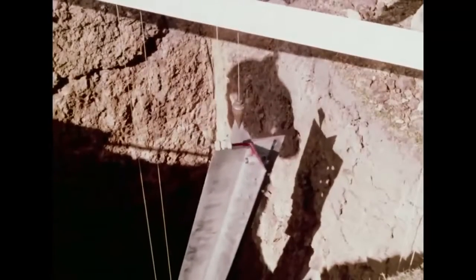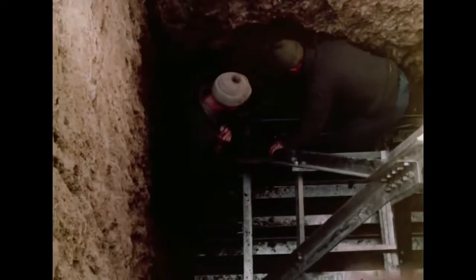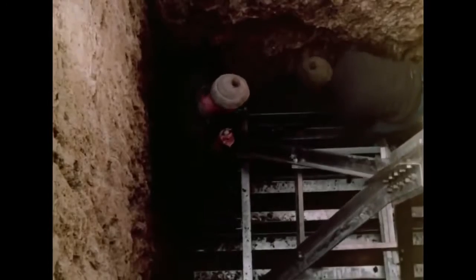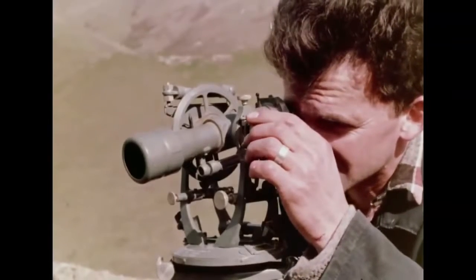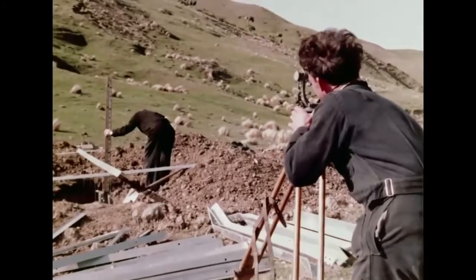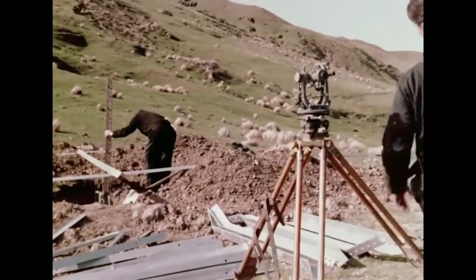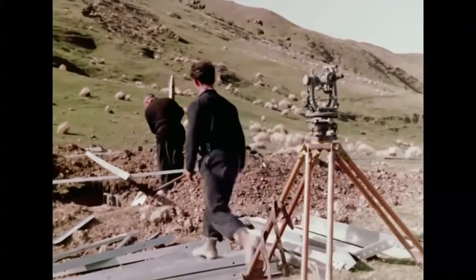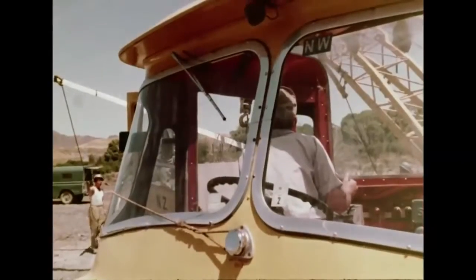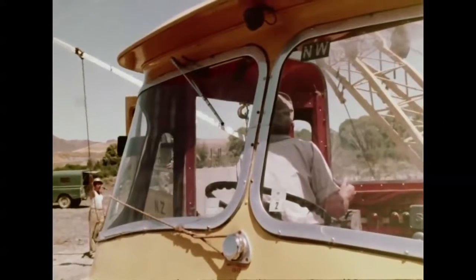Setting of the embedded members of a tower, called stubs on the job, requires great precision. Any difference of level between these steel foundations would make the tower hard to assemble. Furthermore, difference of level would cause uneven stresses and lead to weakness in service. When the stubs have been set accurately in the ground and the holes backfilled, erection of the towers can begin.